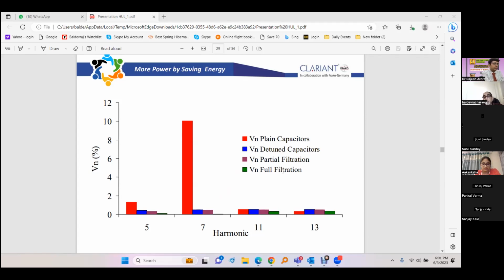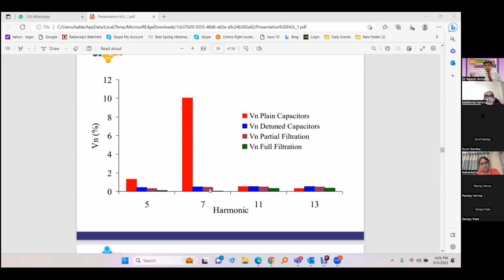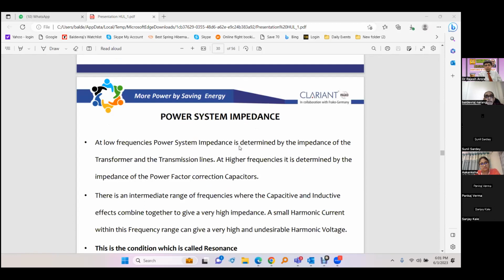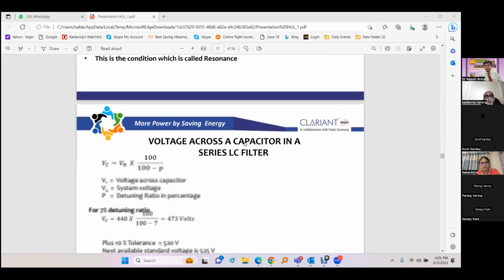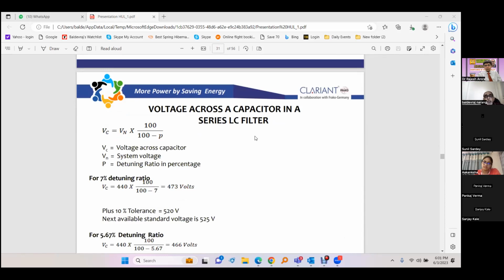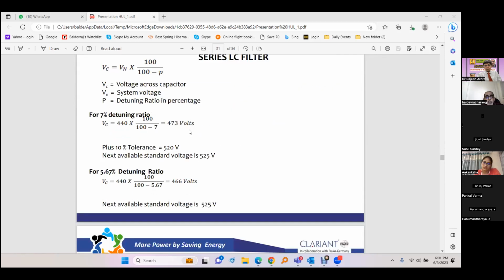But we normally don't use multiple reactors, because when we are using a 7th reactor, there is a chance of harmonic amplification or resonance again at the 5th harmonic. So this has to be carefully designed so that we don't cause further resonance. Then only we use multiple reactors. So this is just an explanation of the curve. I can share the PPTs also, and any questions you can ask later on. So this is how the voltage increase I have shown.